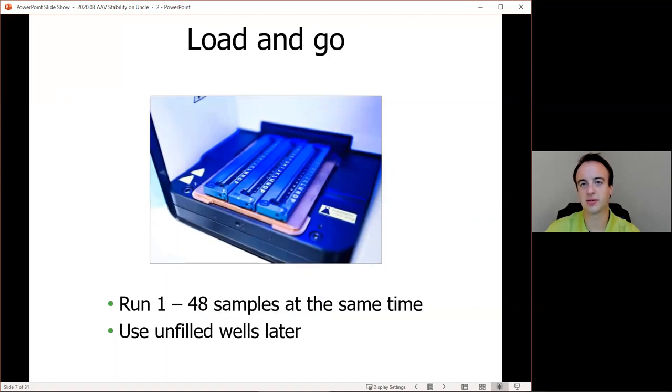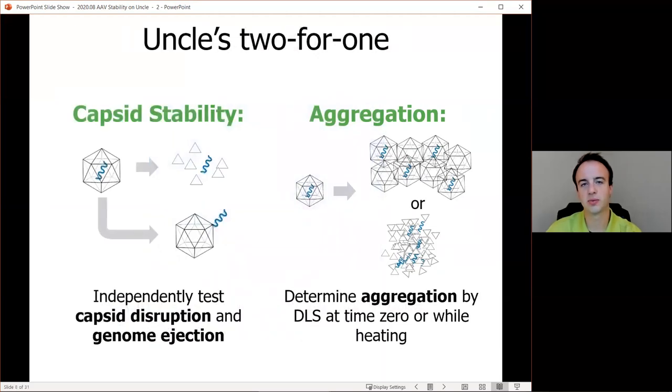Now the UNCLE is ready to test out AAV stability. So let's take a look at what it's going to be used for. So with AAVs on UNCLE, fluorescence can be used to measure two different behaviors for capsid stability, either first shown on the left, proteins unfolding and capsid disruption occurring as a result, or lower shown on the left, genome ejection occurring from capsids. We'll look at data both from the literature and from UNCLE to demonstrate these behaviors. With UNCLE's SLS and DLS capabilities, we will also be able to identify when aggregation occurs, either at time zero before an experiment from DLS, or during a thermal ramp from SLS, or even during a thermal ramp from DLS as well if we design the experiment differently.